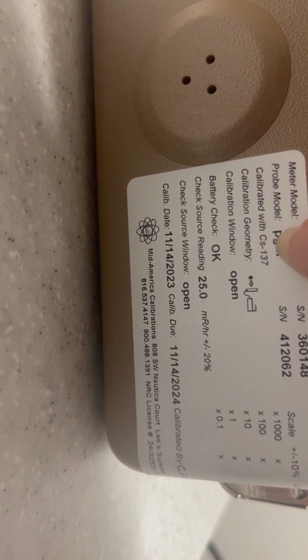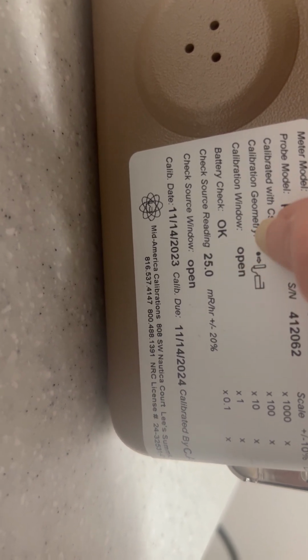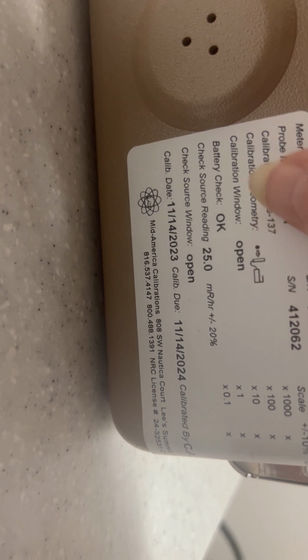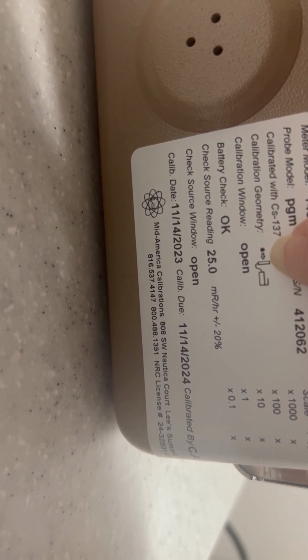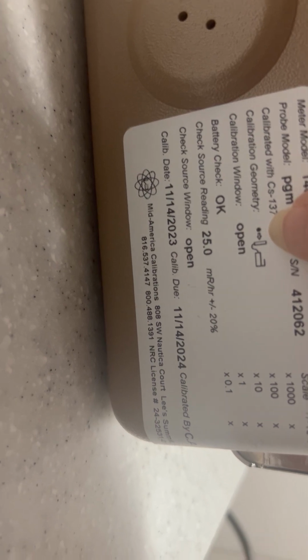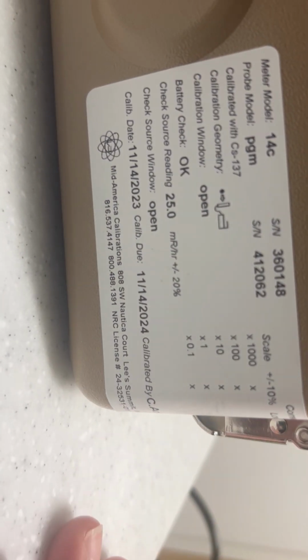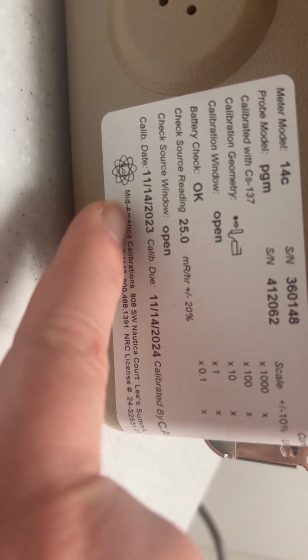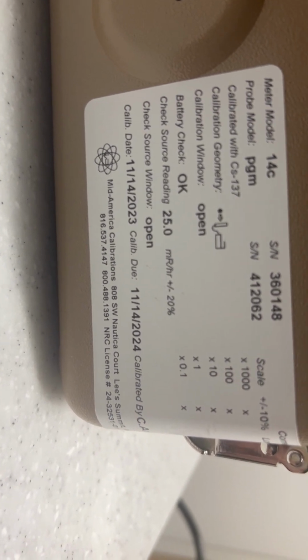Now over here, you'll have the calibration data. So it says it's a model 14C, gives you the probe model. It's calibrated with cesium-137. Geometry is open window, and you want to have the probe window, the pancake, pointing at the source. And then over here, it tells you the calibration date, when the calibration is due, and it will tell you the calibrated amount.